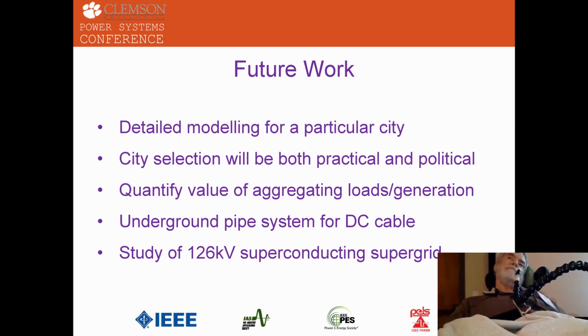One is a pipeline-sized sodium-based conductor that can easily carry 20,000 amps at very high voltage. Of course that's got to be proven, and I've never managed to get the funding to prove it. The other is a type of DC circuit breaker. Those are the two key things needed to enable a supergrid.